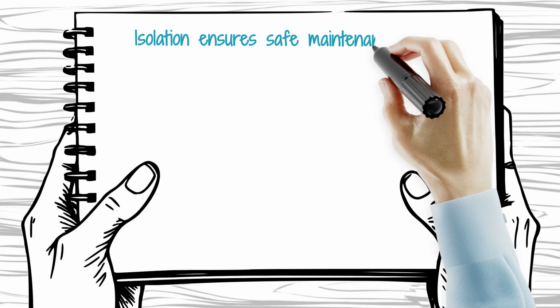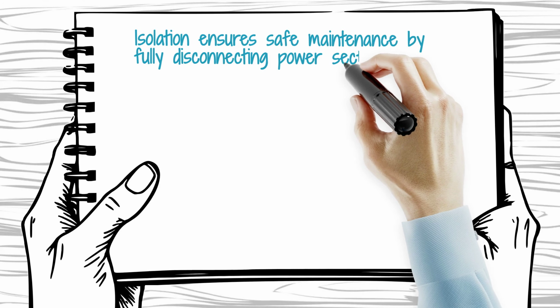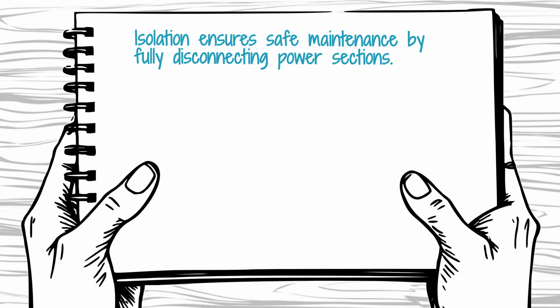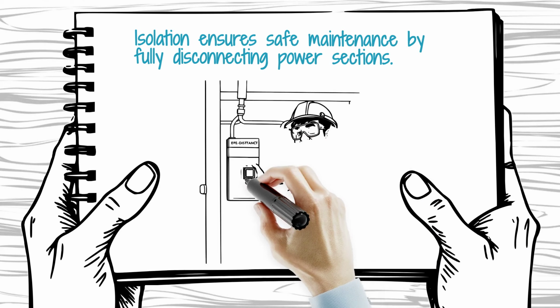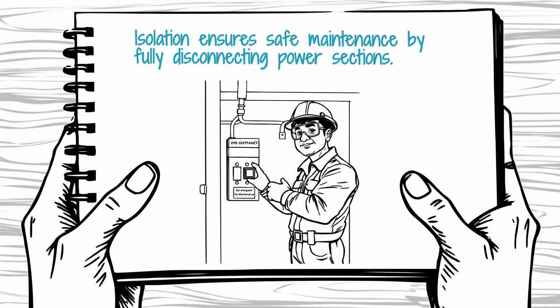Isolation is for safety. It ensures that when maintenance is being performed, the section of the switchgear being worked on is completely and visibly disconnected from all possible power sources, including generator inputs and bus ties. This is achieved using disconnecting switches or isolators, which are opened only after the main circuit breaker has already opened and the circuit is de-energized.